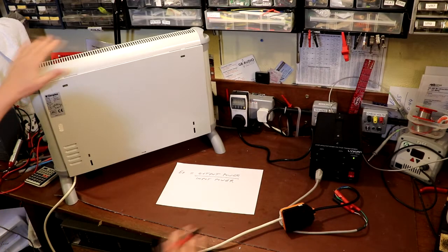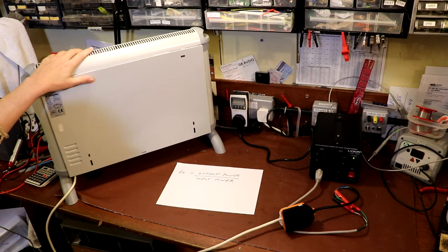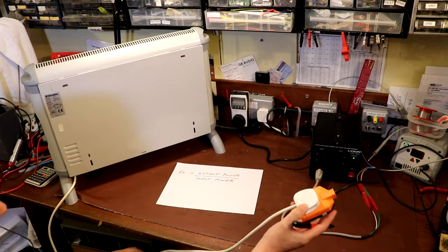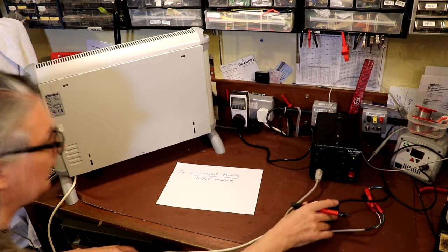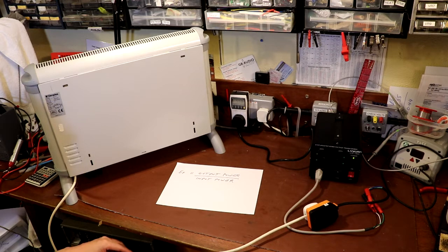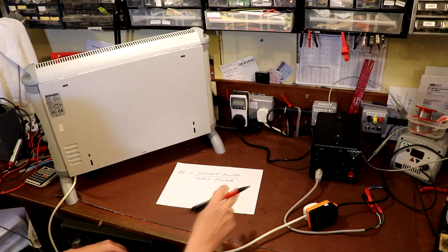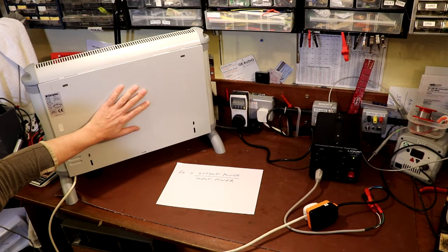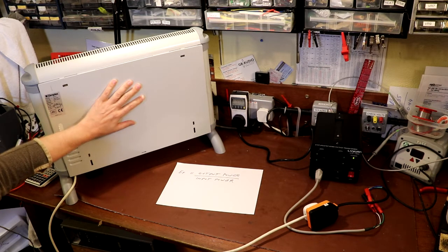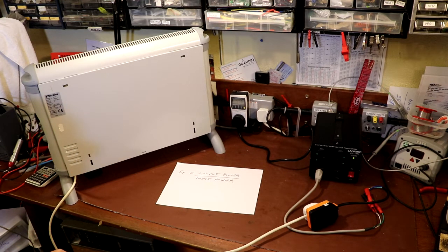I've put this radiator on the bench so you can see what I've been using for testing, plugged into the 110 volt output from our transformer. Really, a transformer efficiency test should be done at full rated power, which for this one is around 1000 watts. Unfortunately, this radiator only creates a 500 watt load, so it's all I've got, meaning our efficiency figures are likely a bit higher than they should be. Typically we'd expect transformer efficiency to be in the region of 92% to 98%.